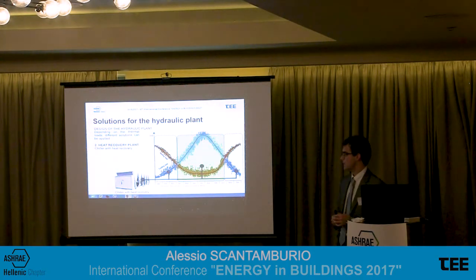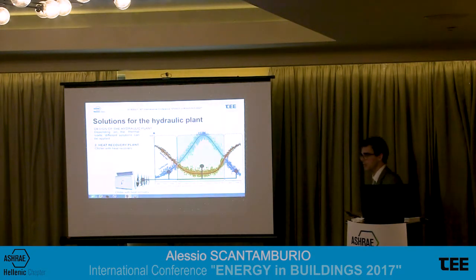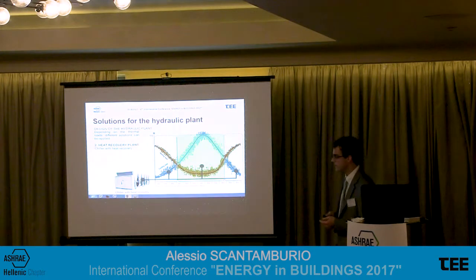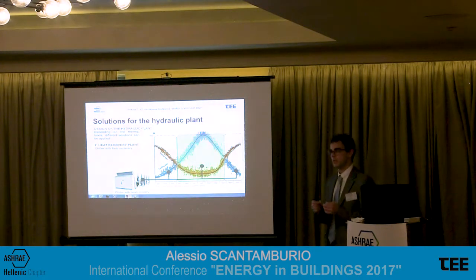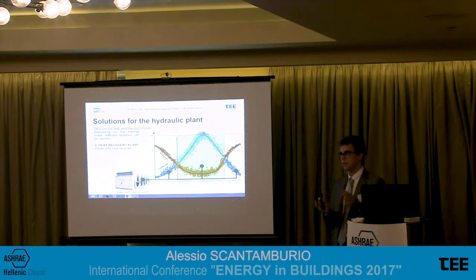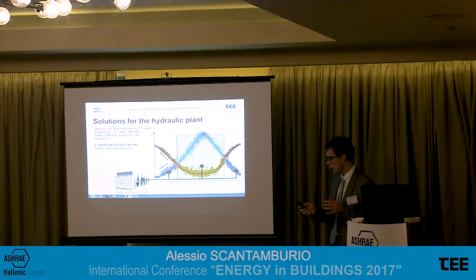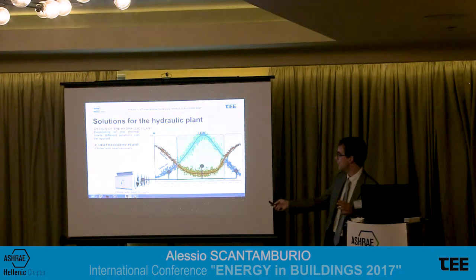A step further is using a chiller with heat recovery. A chiller with heat recovery is a technology that allows producing a certain amount of hot water while the chiller is producing cold water. So with the chiller with heat recovery, we are able to fulfill the building inside this yellow area here.